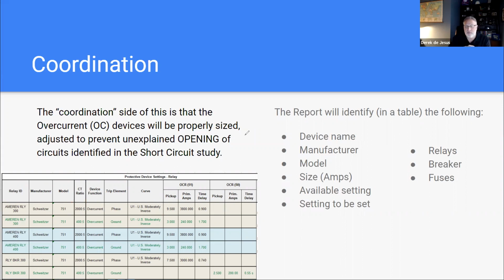Now, some contractors will require the factory to test those breakers, but we should always advocate for the owner that we test at least a sampling, if not all, the breakers on site. There is a time saving in doing them at the integrator as opposed to the site. And sometimes you just have to take what you get, right?